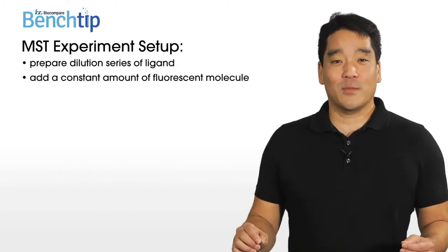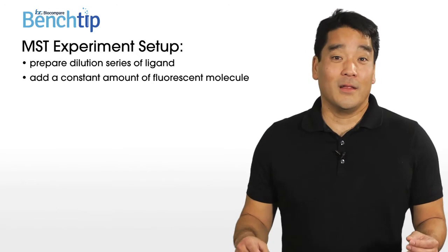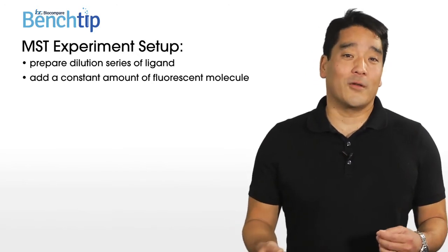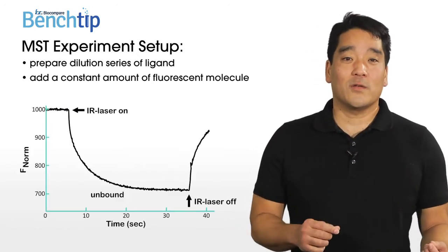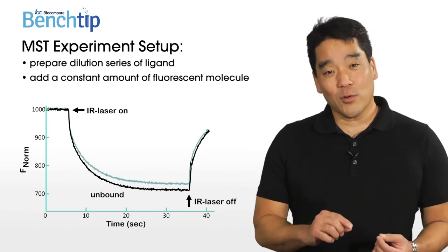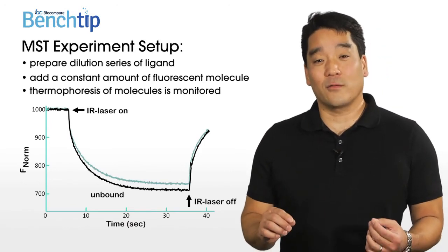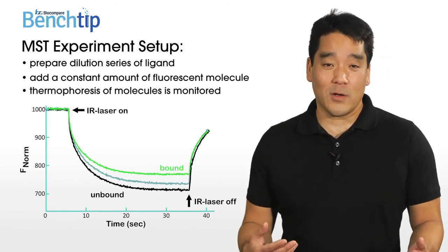So how do you set up an MST experiment? Well, first you prepare a dilution series of your ligand, and you add a constant amount of a fluorescent molecule. The sample is filled into capillaries and loaded into the instrument, and the instrument uses an IR laser to generate a temperature gradient, and the thermophoresis of fluorescent molecules in this gradient is monitored.